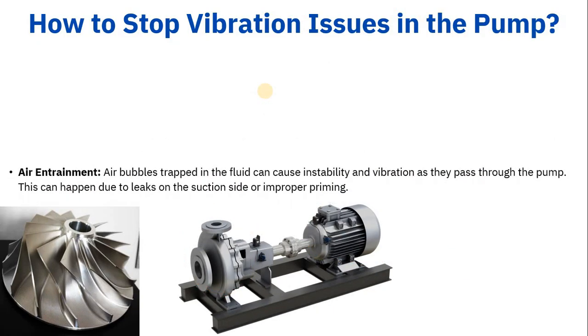Air entrainment is also a cause of vibration. If air bubbles are trapped in the fluid, they create instability and vibration as they pass through the pump. This can happen due to leaks on the suction side or improper priming. If air or gas is entrained or trapped within the suction side of the pump, it creates unstable conditions and reduces flow. That is why we always ensure proper priming — filling the pump with liquid so all air is completely removed.